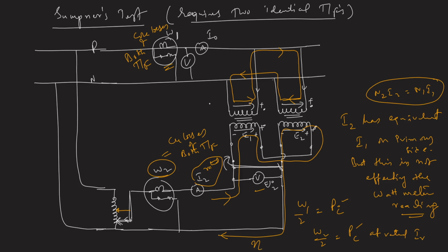Okay, so the advantage here is we are simultaneously doing both the open circuit and short circuit loading conditions of the transformers together, so that the core losses now give me appropriate core losses under full load operating conditions, because under full load operating condition you have the opposing MMF and then equivalent MMF drawn from the primary, so that is mimicked here, and these two wattmeters give me more approximate values than the open circuit and short circuit test. So this is all about the Sumpner's test.